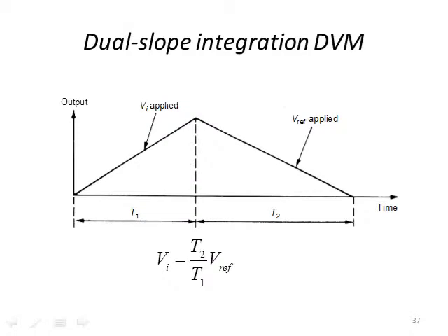Now, in most of these instruments, it uses this dual slope integration to estimate the voltage at the input, even if it's an analog signal, because this thing can actually work with response times on the order of microseconds. So these things actually can respond to megahertz range signals.